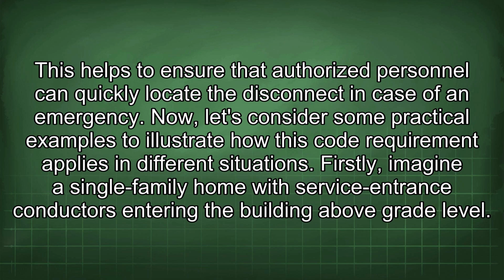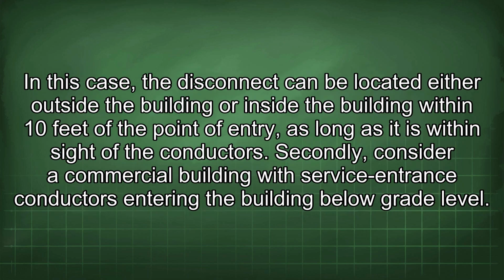Now, let's consider some practical examples to illustrate how this code requirement applies in different situations. Firstly, imagine a single-family home with service entrance conductors entering the building above grade level. In this case, the disconnect can be located either outside the building or inside the building within 10 feet of the point of entry, as long as it is within sight of the conductors.